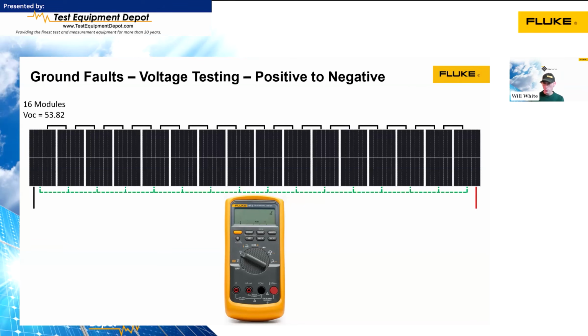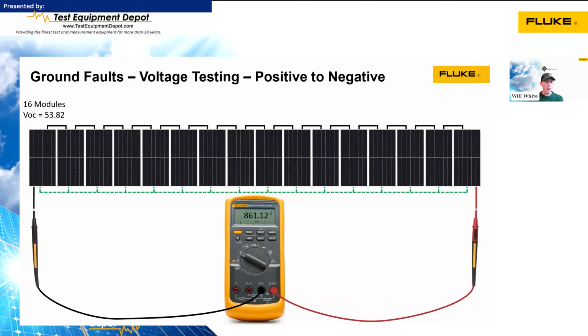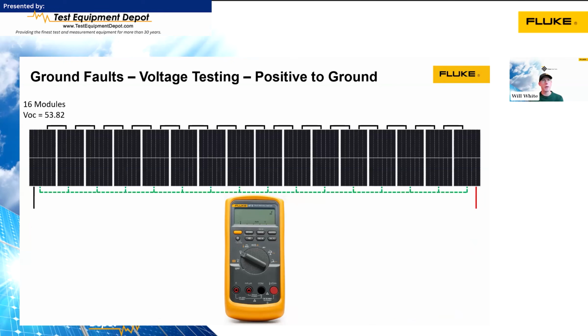Okay, how do I use voltage to test for a ground fault in a string of solar modules? In this example, I've got 16 modules. I've got my digital multimeter. I have an open circuit voltage of about 53 volts per module. If I test from positive to negative, I get approximately 861 volts. I'm going to write that down.